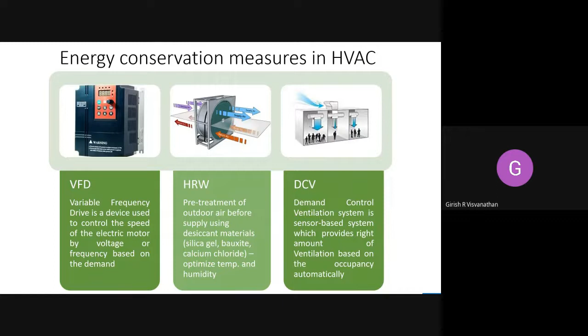Why does this play such an important role? Fresh air coming in, for example in Chennai, comes in at 40 degrees Celsius and 80% humidity. Treating fresh air from 40 degrees and 80% humidity down to 24 degrees Celsius and 60% humidity requires a lot of energy. So instead of continuously giving fresh air, I only give it based on occupancy in the rooms, saving about 15 to 20% additional energy.